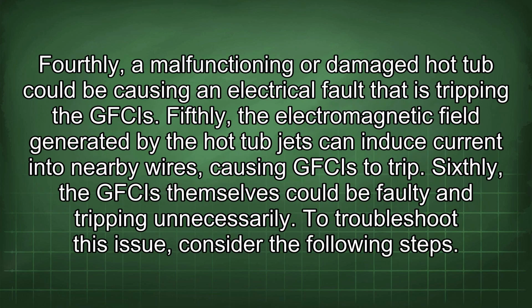Fourthly, a malfunctioning or damaged hot tub could be causing an electrical fault that is tripping the GFCIs. Fifthly, the electromagnetic field generated by the hot tub jets can induce current into nearby wires, causing GFCIs to trip. Sixthly, the GFCIs themselves could be faulty and tripping unnecessarily.